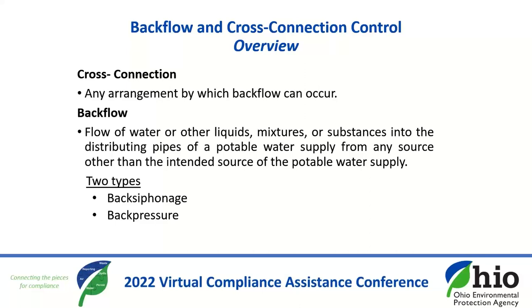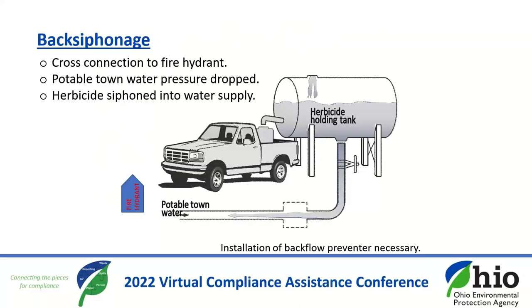There are actually two types of backflow: back siphonage and back pressure. Back siphonage is caused by a negative gauge pressure condition that exists in the water supply piping — essentially less than atmospheric, a partial or full vacuum pressure condition. This can lead to contaminants being sucked into a source, much like taking a sip through a straw. Back pressure is when a contaminant source has a greater pressure than the public water system's pressure, allowing contaminants to flow back into the system. This is an example of a back siphonage condition that actually happened: a cross-connection was created to a fire hydrant connected to an herbicide holding tank, the water supply pressure dropped, and herbicide was siphoned into the water supply.